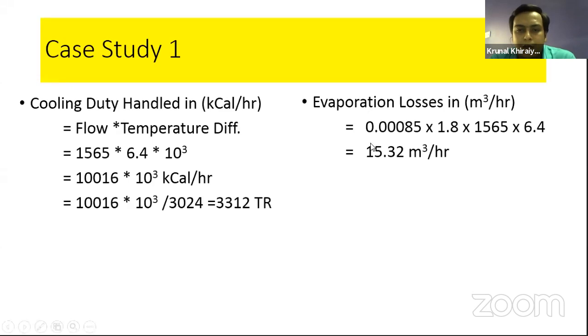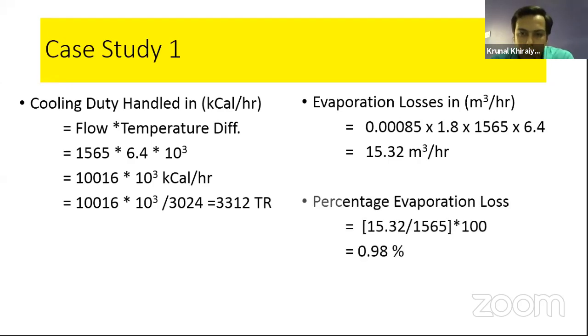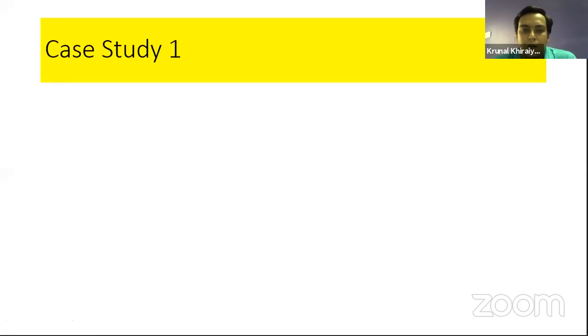The evaporation losses, we are using a very standard empirical formula, 0.00085 into 1.8 into the flow rate, that is 1565, into our range of 6.4. So finally we get the evaporation losses from the cooling tower as 15.32 meter cube per hour. Then the percentage evaporation losses, it means we need to compare. We have a water flow rate of 1565 and evaporation losses of 15.32. So what percentage of evaporation is happening? It is less than 1. So it is a good percentage of evaporation losses that we maintain during the operation of the cooling tower.